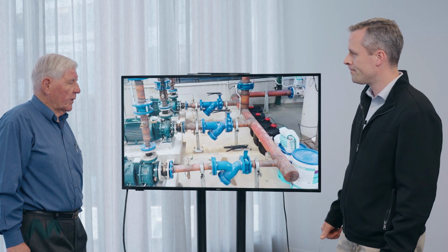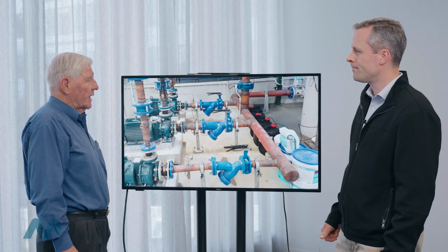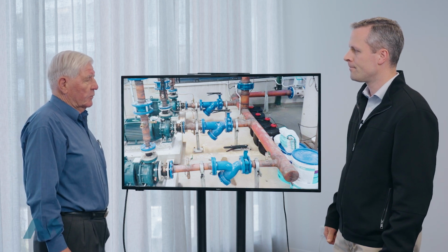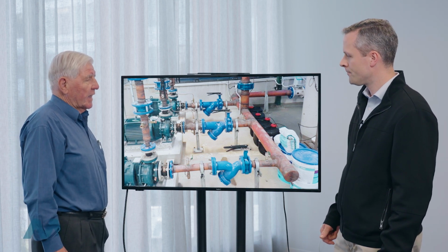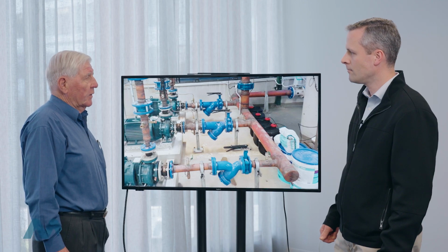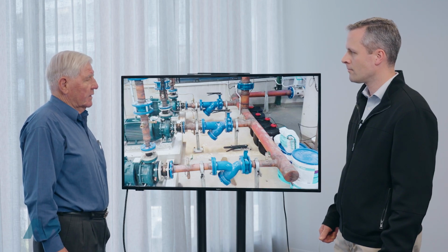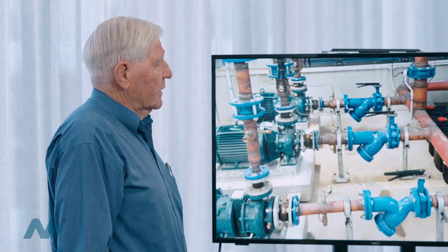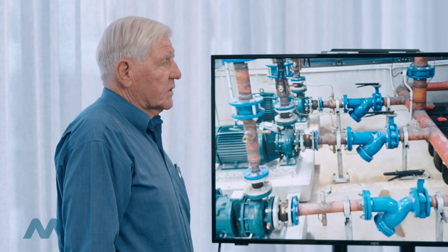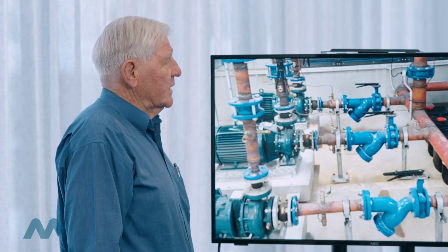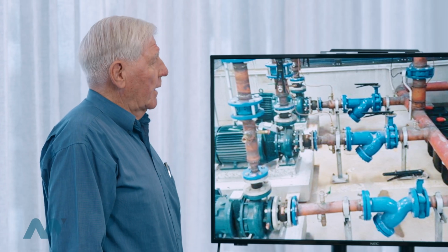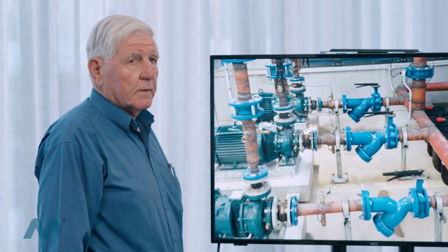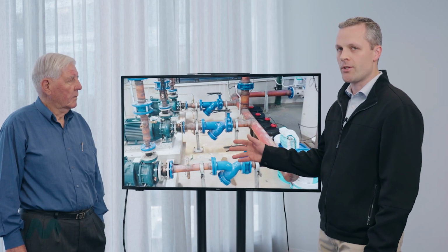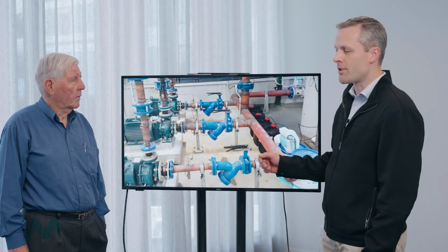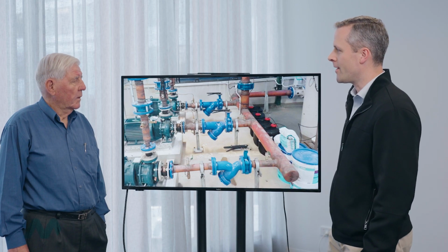Well, generally speaking, I'm looking for relatively low velocities in the suction pipework. They should be lower than they are on the discharge side of the pump. If you talk to various people, they will suggest that 1 metre a second is a reasonable flow rate for suction pipework. So our pipework velocity in this situation was 2.9 metres per second. What are your thoughts around that?